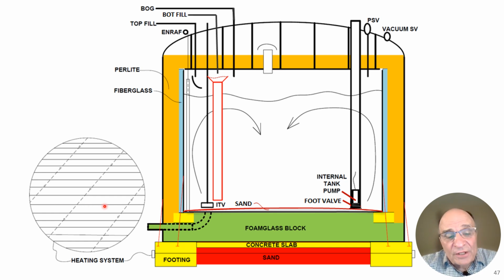Now, if you're fortunate enough, you lose one conduit and you won't lose the second conduit, if it is far away from that. Where it gets problematic is where 2 conduits adjacent to each other or 3 conduits adjacent to each other fail. And that becomes very difficult because then you have to come up with some creative ways to get heat into these conduits.